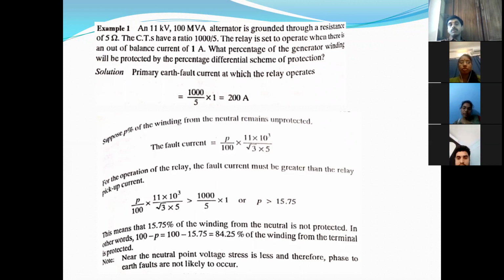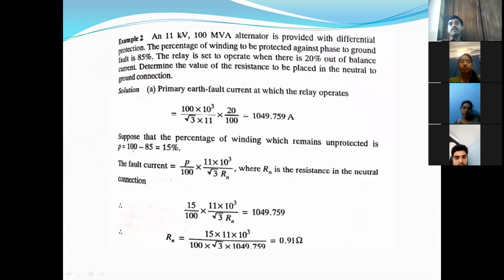Let us see another problem. An 11 kV, 100 MVA alternator is provided with the differential protection scheme. Here they have given that the percentage of winding to be protected against phase to ground faults is 85%. The relay is set to operate when there is 20% out of balance current. That means they have not directly given the primary fault current, only the 20% out of balance current. So determine the value of the resistance to be placed. What is the Rn value in the neutral to ground connection?